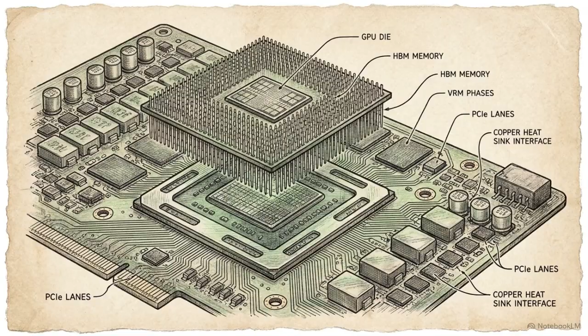That level of compute generates severe localized heat. Traditional air conditioning is physically incapable of moving enough air fast enough to keep these specific racks from melting down. The strategy is direct liquid cooling. Water pipes through cold plates directly onto processors, absorbing thermal energy instantly.